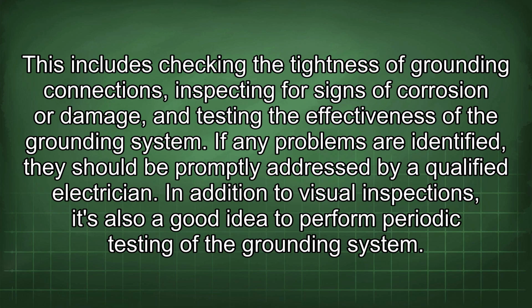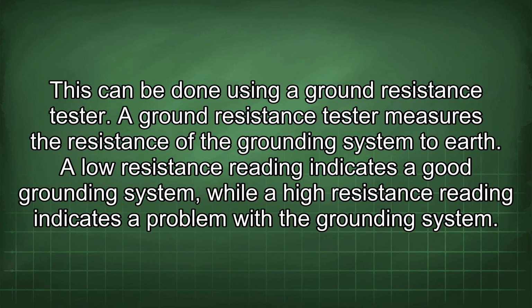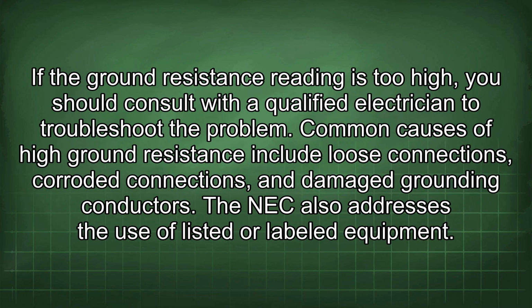In addition to visual inspections, it's also a good idea to perform periodic testing of the grounding system. This can be done using a ground resistance tester. A ground resistance tester measures the resistance of the grounding system to earth. A low resistance reading indicates a good grounding system, while a high resistance reading indicates a problem with the grounding system. If the ground resistance reading is too high, you should consult with a qualified electrician to troubleshoot the problem. Common causes of high ground resistance include loose connections, corroded connections, and damaged grounding conductors.